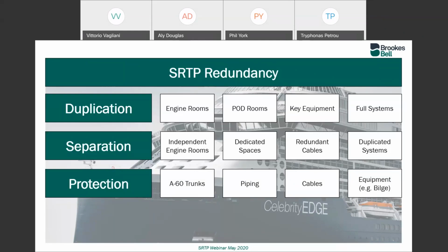Similarly, with cables, we can obviously have fire and flood protected cables, but it's important to note that when it comes to the fire protection side of things, when we're returning to port and we've had a small fire, yes, it may be sufficient for that cable to have an hour's worth of fire protection. However, if it needs to be available for the evacuation process, then we're talking about 3 hours worth of protection. In fact, some class societies push for 5 hours of protection if we're relying on it for the evacuation abandonment process. And obviously some equipment can also be protected in the sense that a bilge pump or a fire main pump may well operate perfectly well underwater.